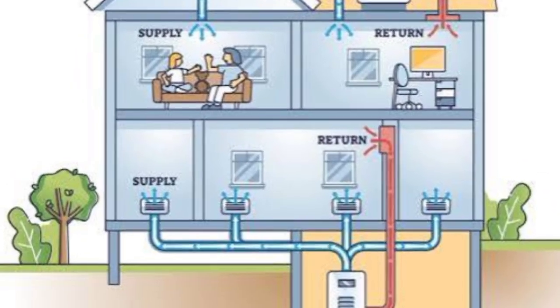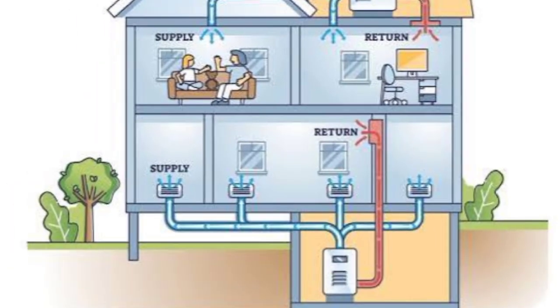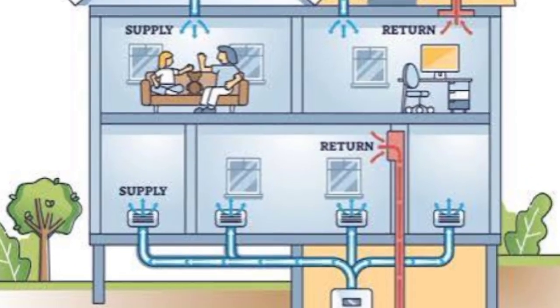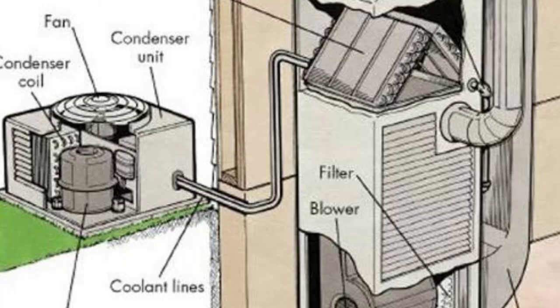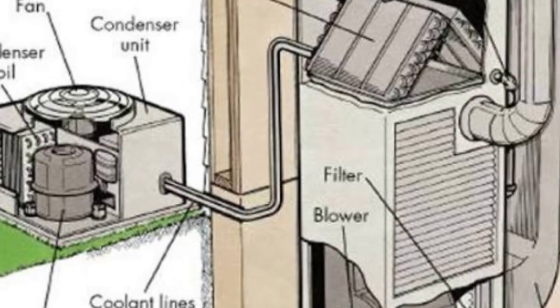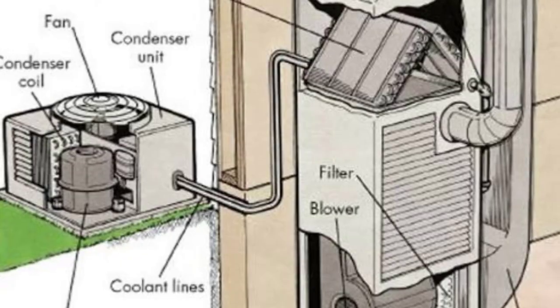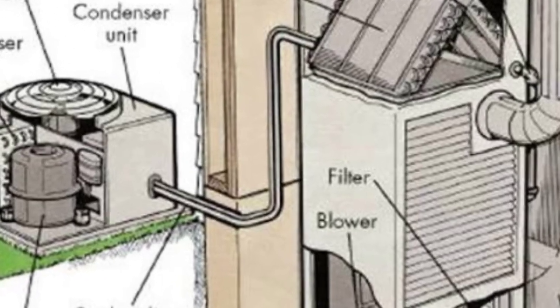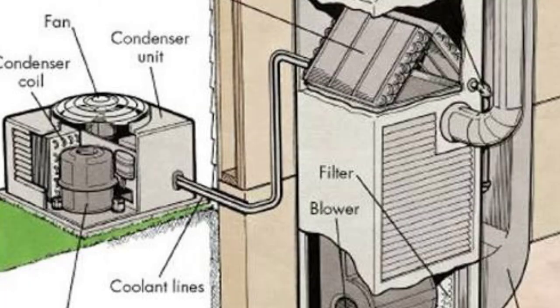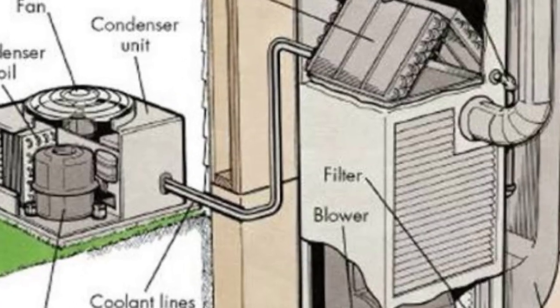Must have been a lemon. They buy another one, same contractor installs it, same rule-of-thumb sizing, and the cycle repeats. The contractors know this, the manufacturers know this, but nobody has any incentive to fix it. The homeowner doesn't know enough to demand a manual J calculation. The contractor makes more money selling larger equipment, and the manufacturer gets to sell two systems in the time one should have lasted.